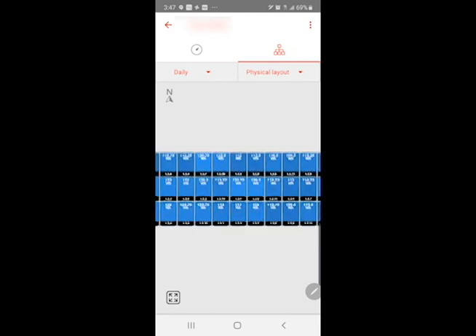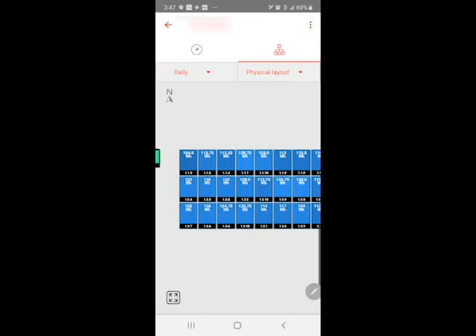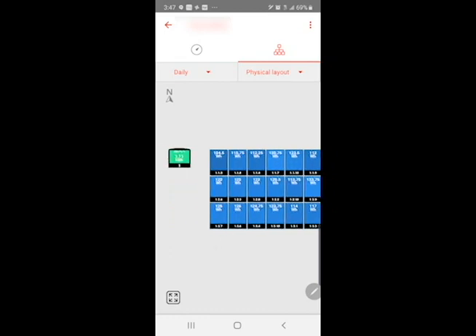If you go up to the layout section, this is going to be a physical representation of the layout on your roof. We complete this for you after the install — if there are any problems, please let us know. Basically, each module is displaying watt hours for that specific module. All the modules are not going to match up 100%, and that's okay. There's shade that happens, there's the angle of the sun at that time of year and how it rises over your system. But this is a great way to see if there are larger issues where modules aren't producing at all, or maybe they're producing at half capacity, and we can assist and see what's going on.